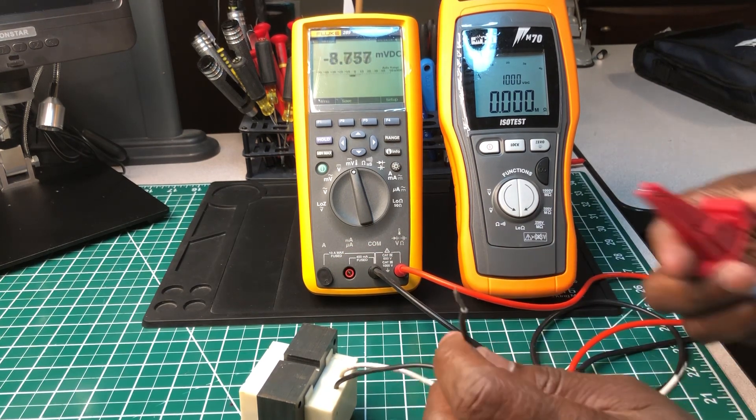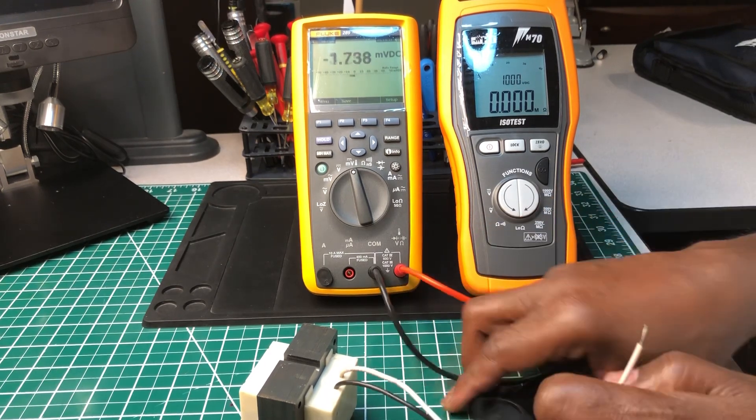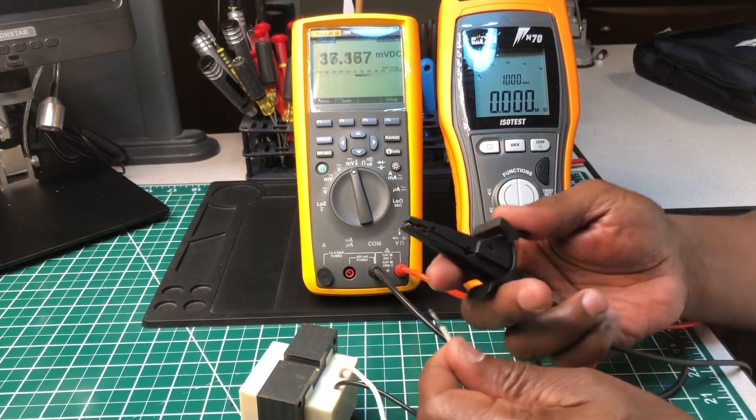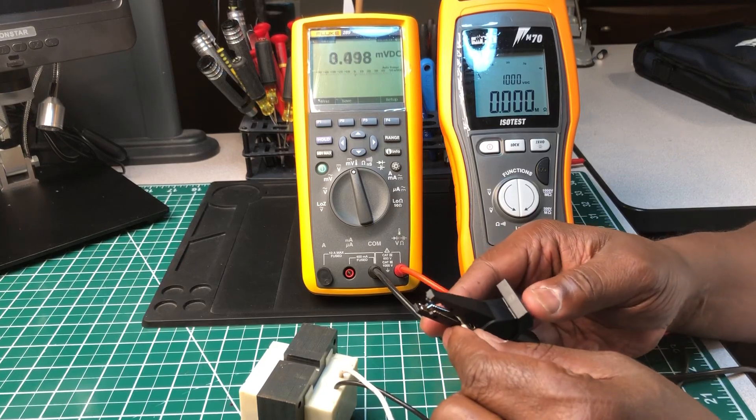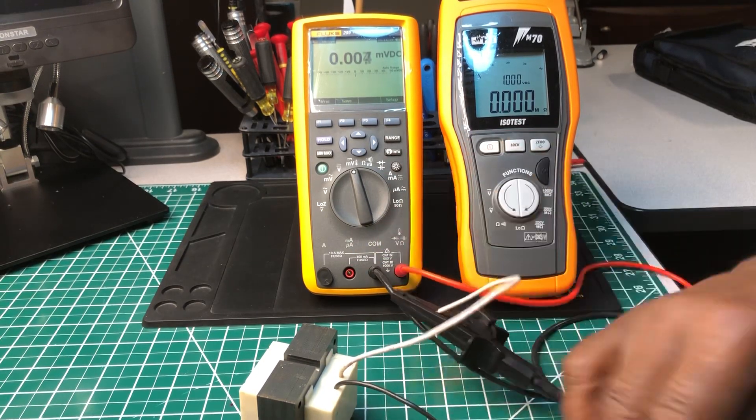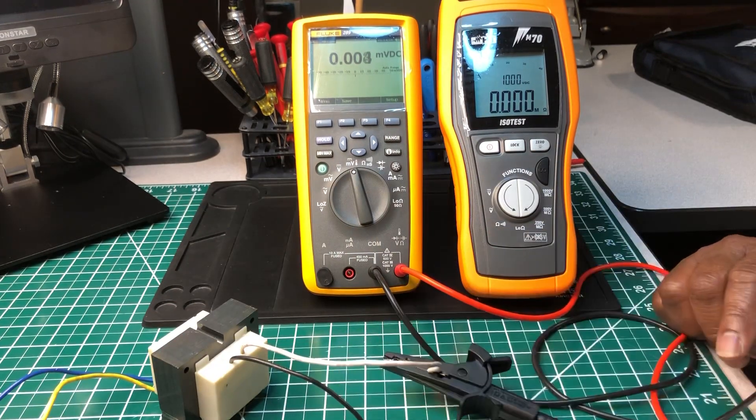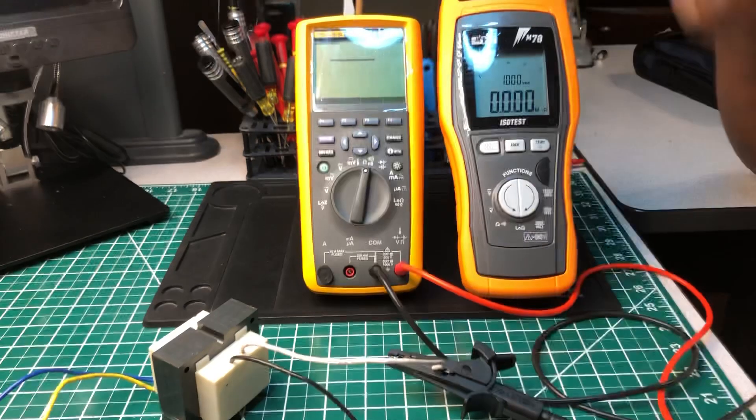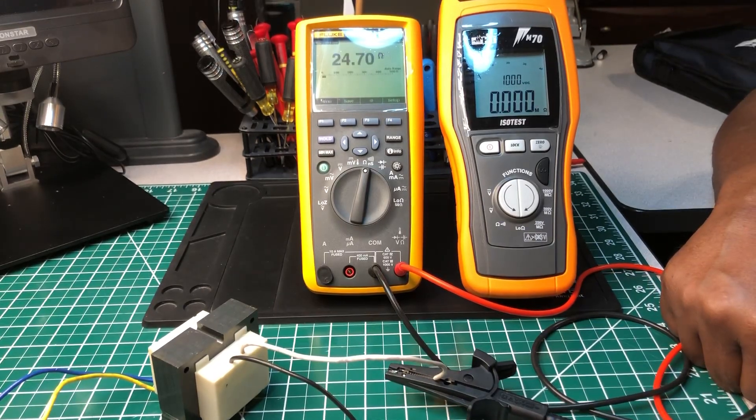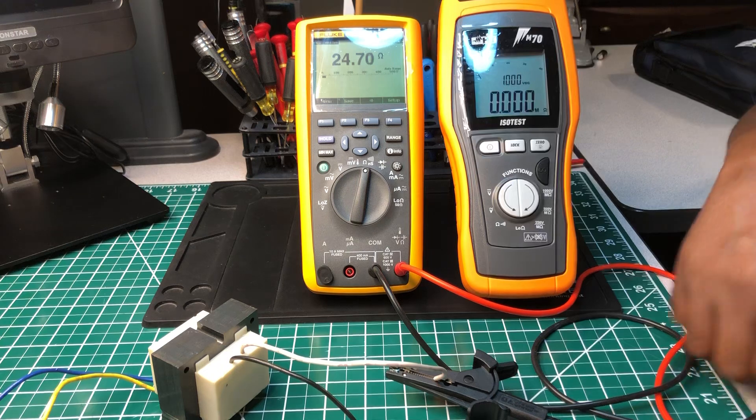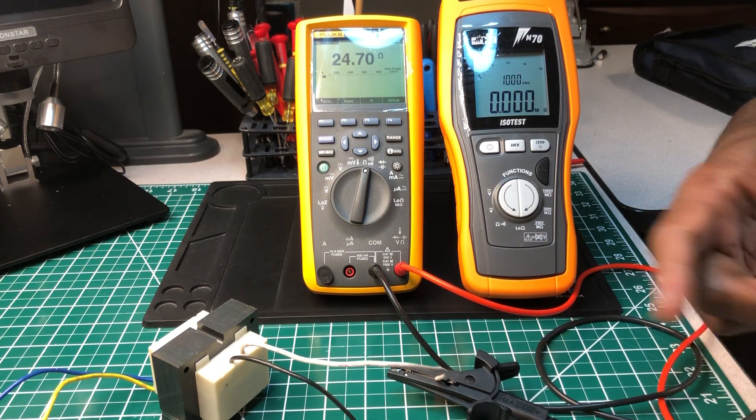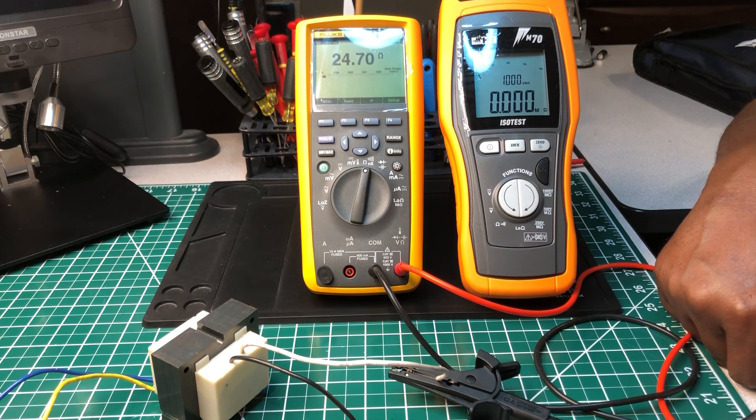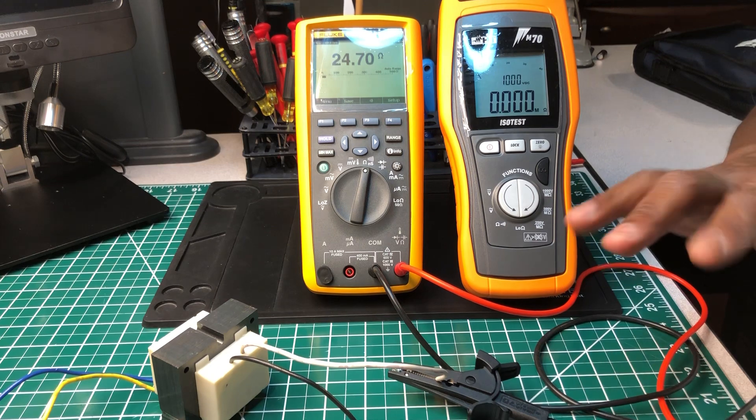We're going to do this. I'm going to put it on. When you put your leads on, it doesn't matter which color you put on which terminal. So we're going to put them on. It's giving me 24.7 ohms resistance, so this transformer is good.